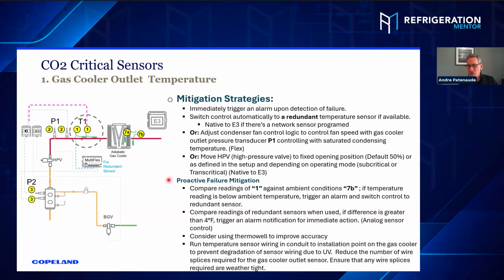But there's some proactive things too that could be done before this even happens. You can compare the reading of T1 against 7B. So the gas cooler outlet temperature measures itself against 7B, the ambient. If T1 is lower than 7B, it should never be lower because it's picking up heat through the gas cooler. So if it's lower, then something's wrong, either with 7B or T1. And you send an alarm, you get somebody in to check it out before the system crashes, because nothing's gone wrong yet. It's just that you've got an imbalance in numbers.